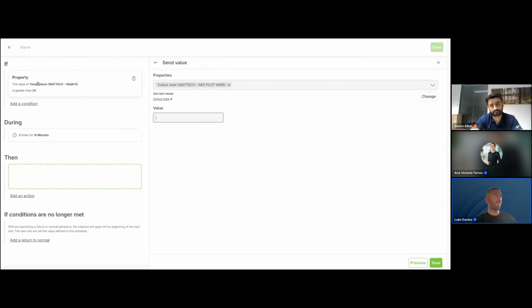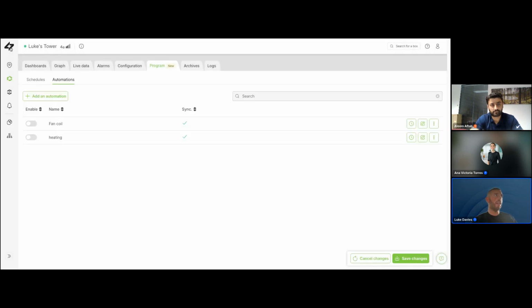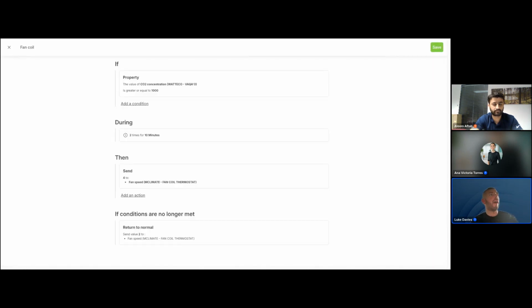So you have the opportunity here to define all your individual parameters for this to work. You can name it whichever you like, and it's the same as a scenario if we were to use a fan coil unit, let's just say. So if the CO2 concentration in a building is equal to or greater than, let's say, 1,000 ppm, and that happens 2 times in 10 minutes, then we send the value 4, which would operate the fan speed of the fan coil unit. When the conditions are no longer met, we return to normal, and you can just play around with that.